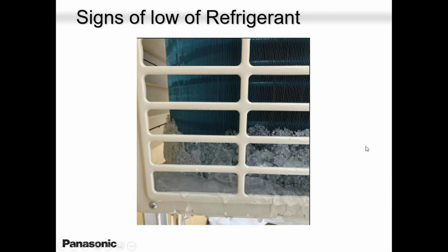These are small units, critically charged, very small units. You weigh in their charge. So the moment you go away with 6-7 ounces, you're in trouble. The unit is in trouble. So the last thing you want to do is hook up your gauges. The first thing you want to do is temperatures, running amp, and take it from there.